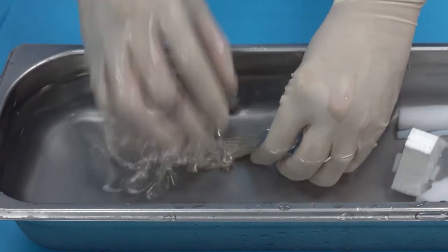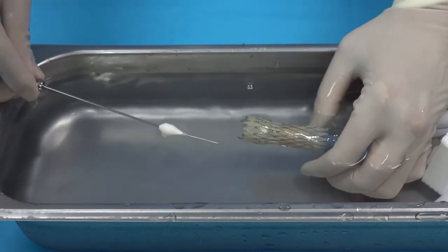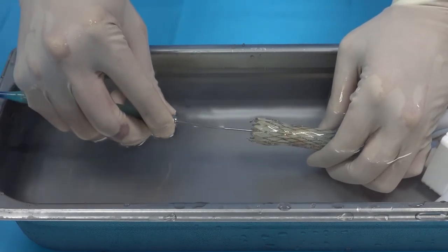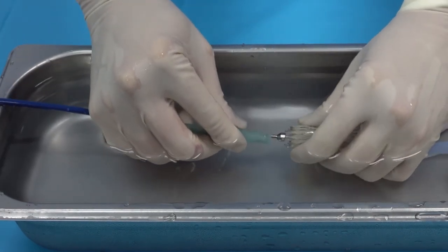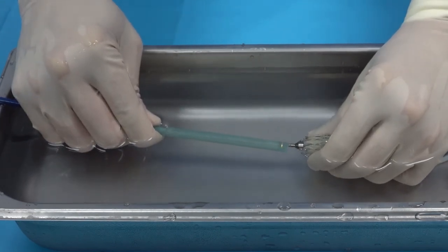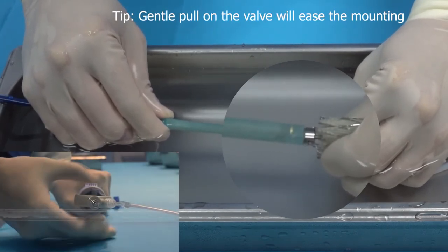Hold the P-valve with the left hand and hold the head or carrot of the delivery system with the right hand and insert into the protection tube. In this demonstration, the protection tube is just inside the inflow end, but preferably outside of the inflow end to avoid damaging the valve. Lock the two hooks or ears at the inflow end of the P-valve to the raised U-shaped lock key on the delivery system.